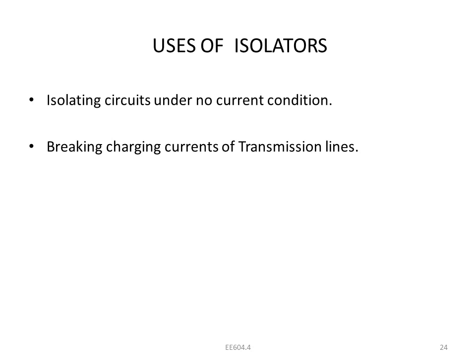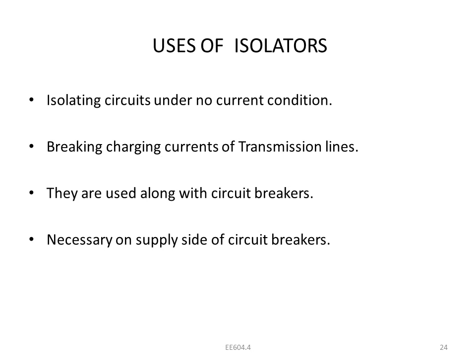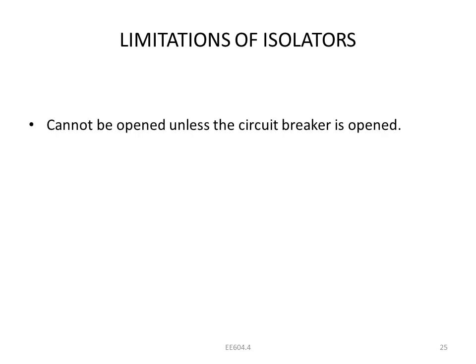So you can see. The uses of the isolator: isolating the circuit under no load conditions, and breaking the charging current of transmission lines. They are used along with the circuit breaker, but it should be operated under no load condition. The circuit breaker handles load and fault conditions, and manual operation under load is a different matter. The isolator is on the supply side of the circuit breaker, used if any variations are made for maintenance purposes. There are limitations to these isolators: they cannot be opened unless the circuit breaker is open.